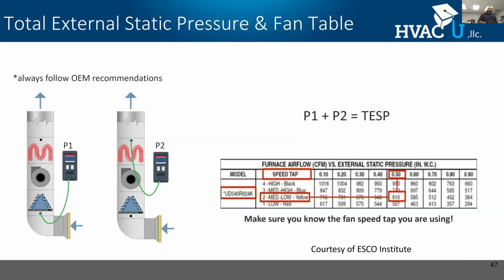The way we get airflow, manufacturers profile the heat exchanger. They run a heat exchanger through several flow characteristics, and they plot the static pressure. When they plot the static pressure, they give you a way to take that static pressure information and come up with an airflow in CFM. Now, this is great for new equipment. However, one of the disadvantages is that as this equipment starts to foul, or if there's any kind of neglect, this becomes less accurate. So it's more accurate on newer systems. It's a way to get airflow, but just know if the system has been existing for some time and there's any kind of dirt loading, this may not be the best method to get system airflow.